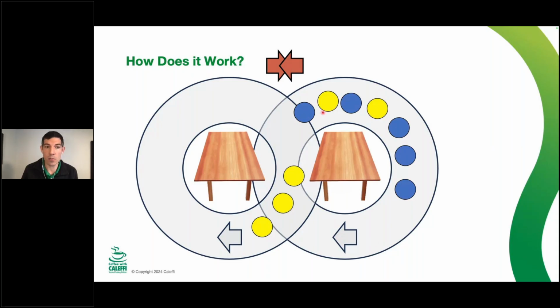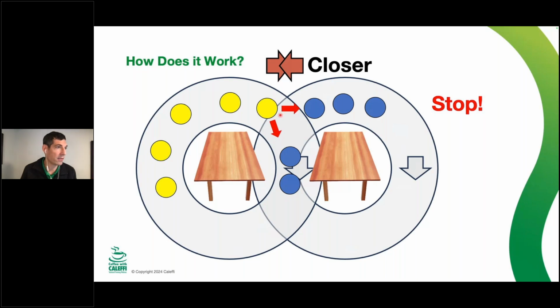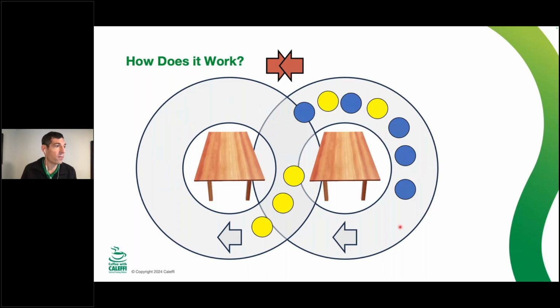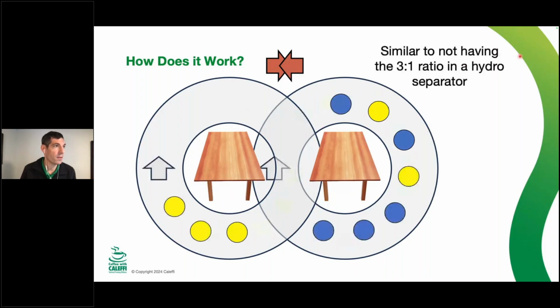Now we don't have the balance that we thought. We have people joining the wrong circuit, and that's influencing the flow at this decision point, as if you were a molecule of water or glycol or whatever, that you have to decide, is it easier to go left or right here? And that's what happens when primary, secondary rules are broken. We now have more flow, more people in this analogy, on the right side than we do on the left side, and we're breaking our rules with primary, secondary piping by not having that golden 3-to-1 ratio anymore because we squeezed it closer together.